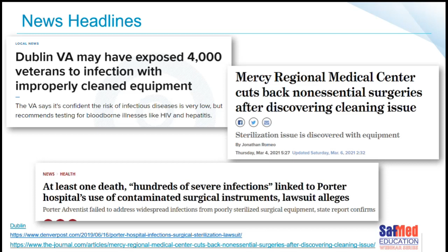Imagine this. Dublin VA may have exposed 4,000 veterans to infection with improperly cleaned equipment. Mercy Regional cuts back on non-essential surgery after discovering a cleaning issue. Here we have at the Porter Hospital at least one death, hundreds of severe infections linked to Porter Hospital's use of contaminated surgical instruments. Lawsuit alleges. Lawsuit. This is a very important concept. It may seem so simplistic, but cleaning is actually so important. This particular journal publication is called Complex Design of Surgical Instruments as a Barrier for Cleaning Effectiveness, favoring biofilm formation.